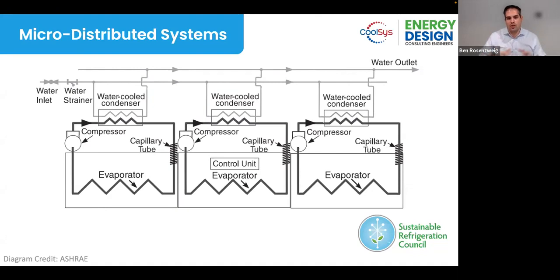So where you see the water cooled condenser on the top there, that could be replaced by individual air cooled condensers, or you could have a central hydronic water glycol loop through your store that you're using to reject the heat from these systems and take it outside to a dry cooler or other piece of equipment. Next slide, please.